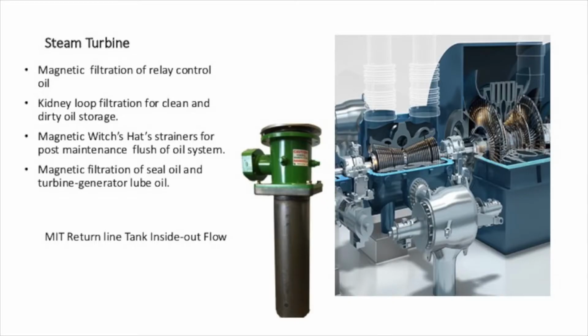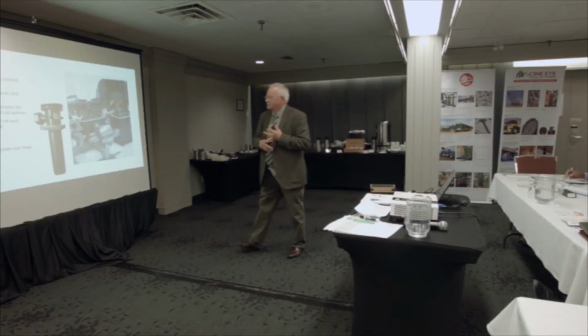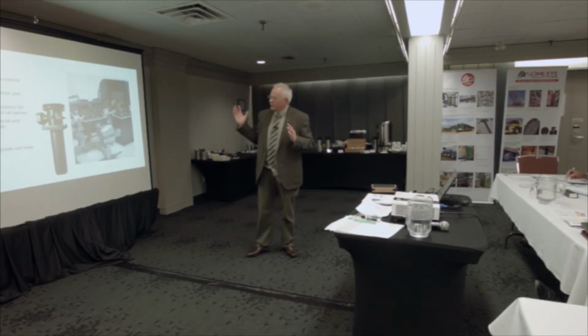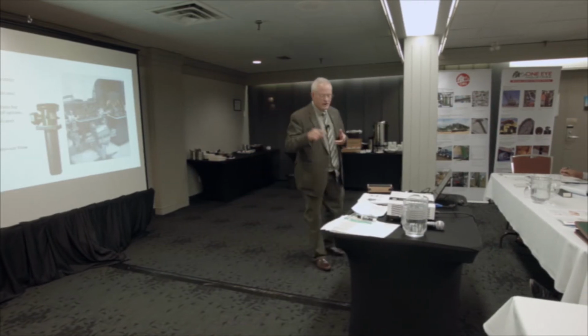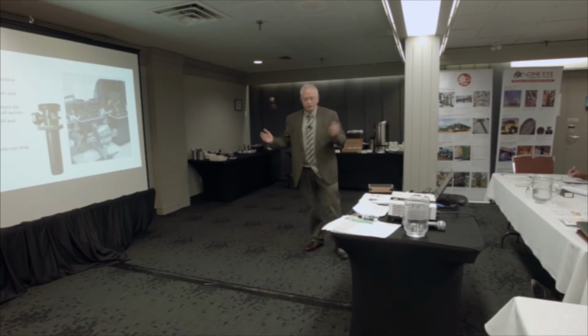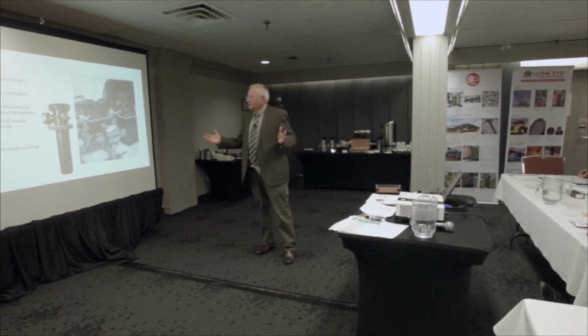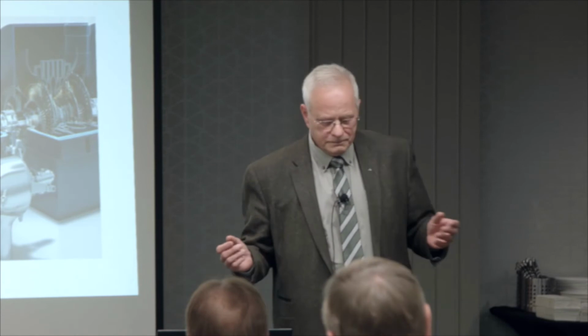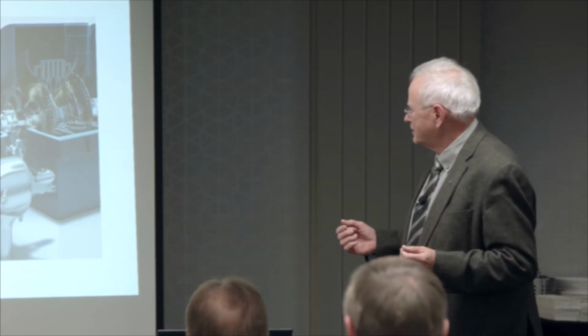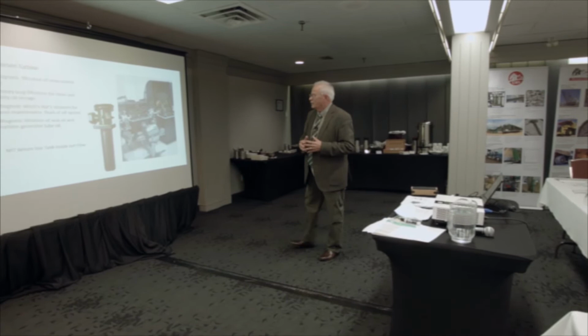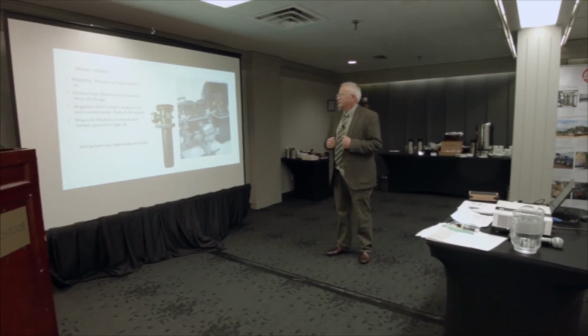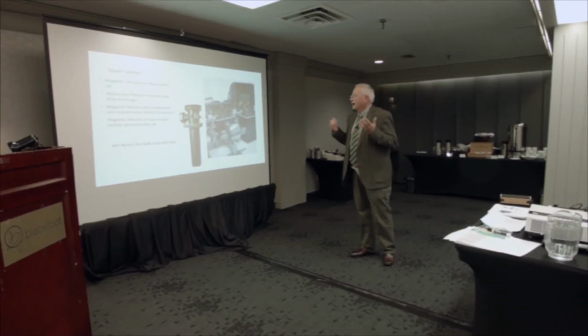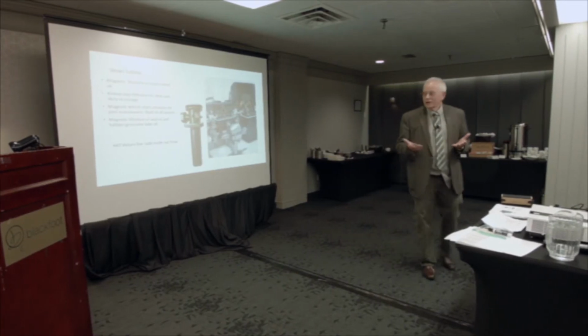Steam turbine. We have a 4,000 or 8,000 gallon storage tank of oil. That oil, Teresso 32, supplies the complete turbine system: lubrication, hydraulic control on your valves, your front pedestal, your overspeed bolts. It supplies the generator with oil, lubrication, and sealing. So this one oil supply is extremely important to keep clean. Unfortunately, we struggled with this all the time.